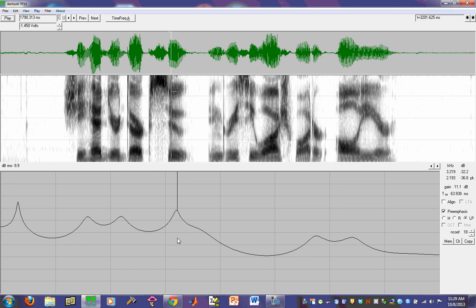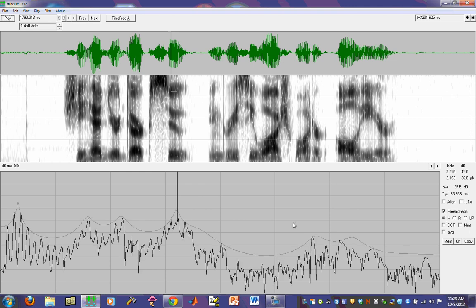Now, you can display both multiple images on the spectrum display by using this button down here called the memory key, or memory button. And what it will do is it will record the display right now, and then if you go back, for example, to the FFT spectrum, you can see that it has both of them are displayed. And this is useful for seeing for multiple displays where you are interested in both information, perhaps, about the fine structure as well as the broader pattern of where the energy is concentrated across frequencies.